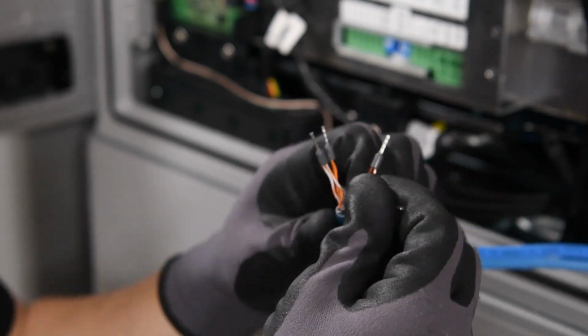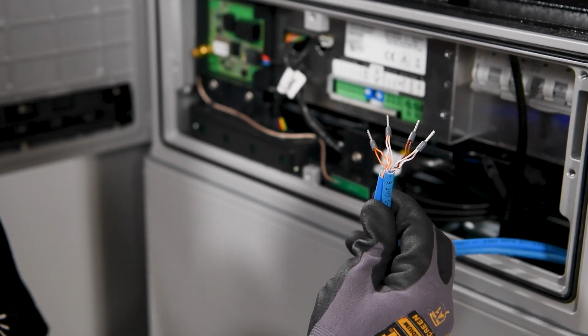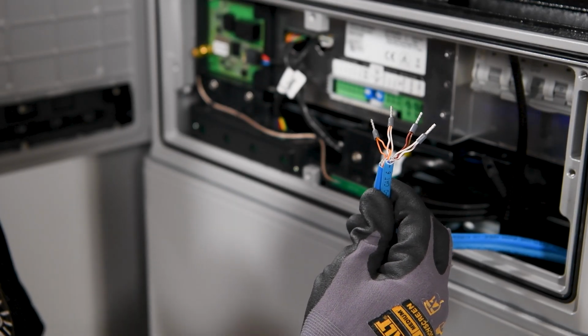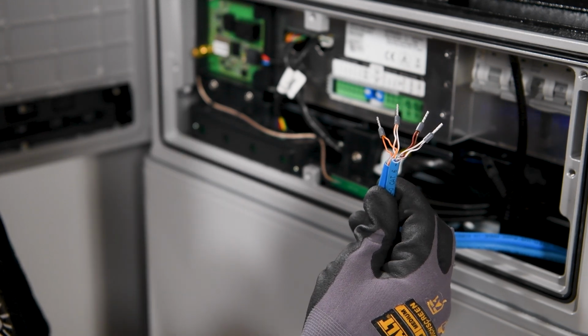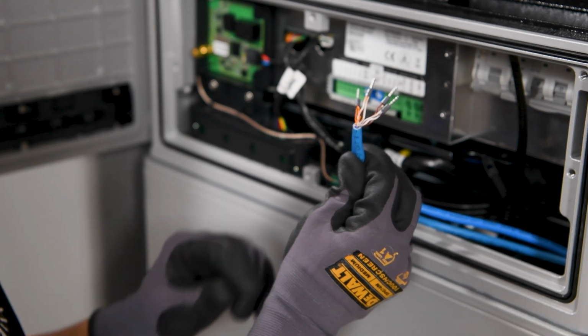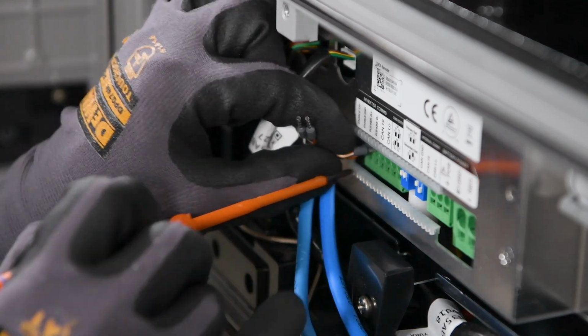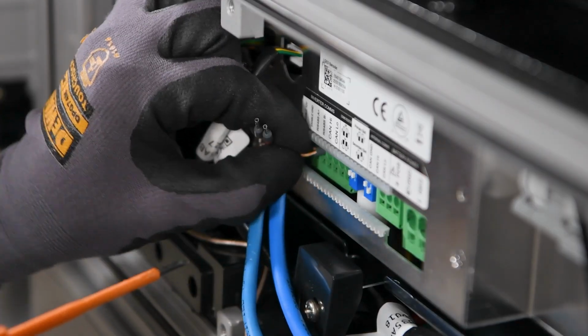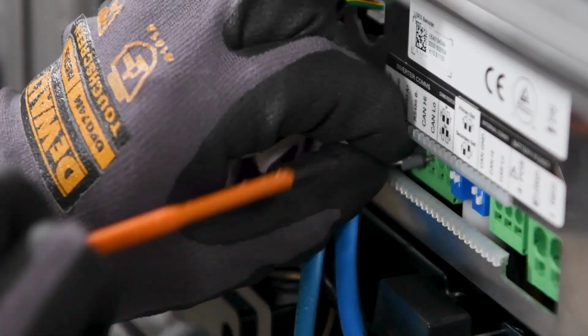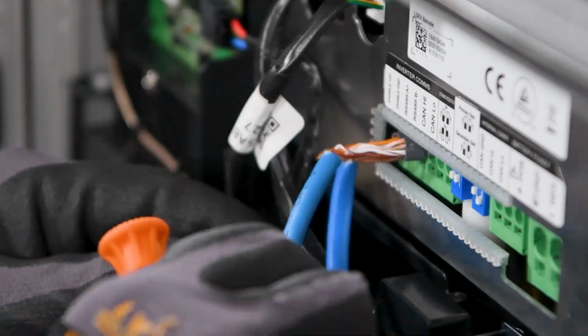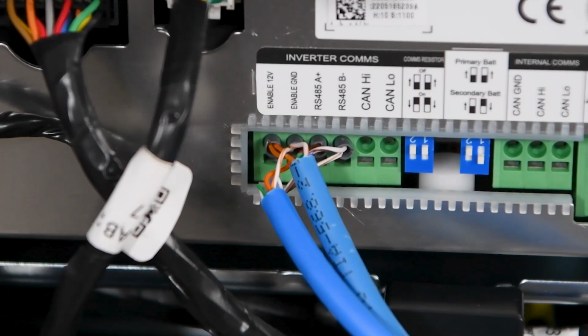I've combined each of these communication wires with ferrules, which makes it easier to insert into our communications port. Both batteries will then be connected to the inverter and communicating: orange to enable 12 volt, orange white to enable ground, brown to RS485A+, and brown white to RS485B-, the same as everywhere else.